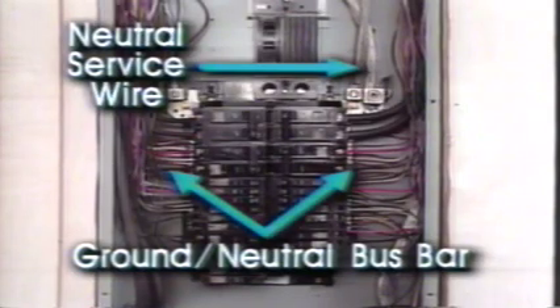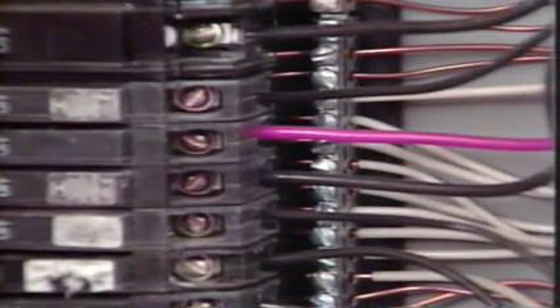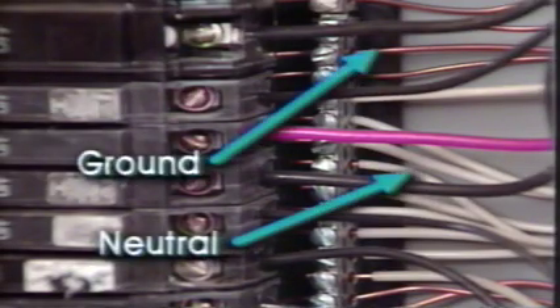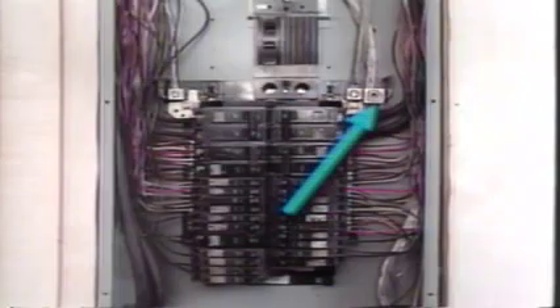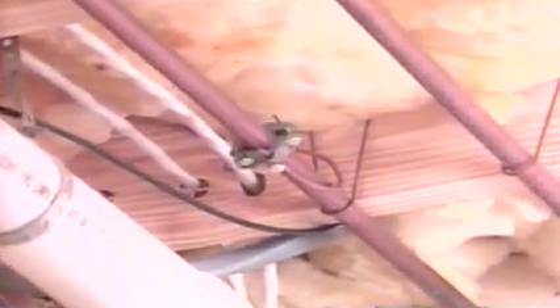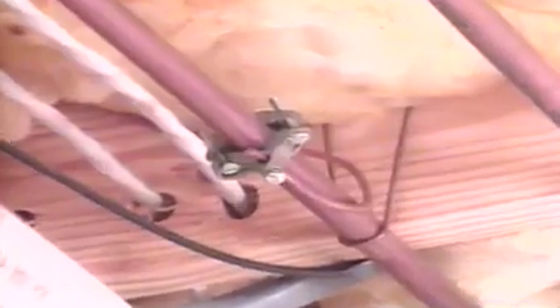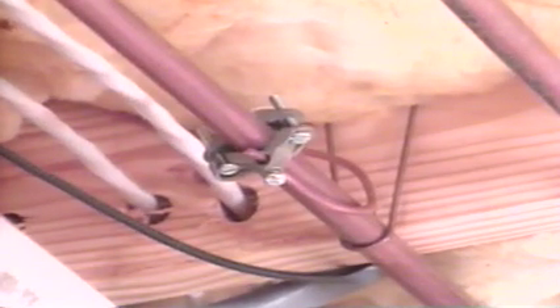The neutral service wire is attached here to the ground neutral bus bar. This is where all neutral and ground wires from the individual branch circuits are also attached. All ground and neutral wires terminate at the ground neutral bus bar in the distribution panel. The distribution panel is also grounded to the ground neutral bus bar. This ground neutral bus bar is grounded to earth either by attaching to a metal water pipe inside the house or to a copper rod driven into the earth outside the house as close as possible to the meter.